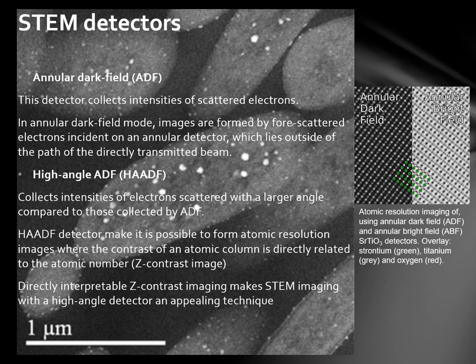ADF detectors collect intensities of scattered electrons. In annular dark field mode, images are formed by scattered electrons incident on an annular detector which lies outside of the path of the directly transmitted beam. High-angle ADF collects intensities of electrons scattered with a larger angle compared to those collected by ADF. HAADF detectors make it possible to form atomic resolution images where the contrast of an atomic column is directly related to the atomic number. Directly interpretable Z-contrast imaging makes STEM imaging with a high-angle detector an appealing technique.